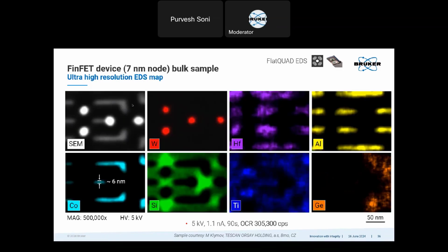And this is a bulk FinFET semiconductor sample, and it was measured at 5 kV and probe current of 1.1 nanoampere. And we can see the very high count rate of 305,000 counts per second. And because of this very high count rate, I only had to measure for 90 seconds, and I could get a very good statistic map. And I could even resolve a feature which was around 6 nanometer in size.